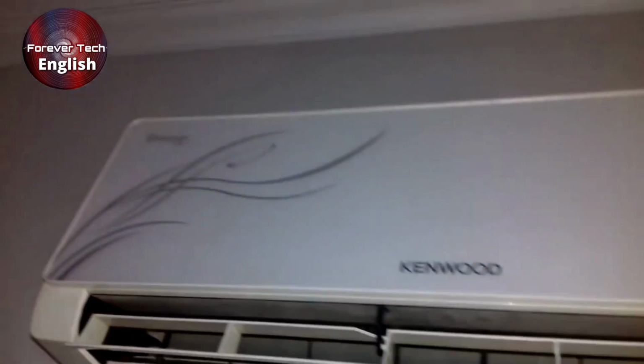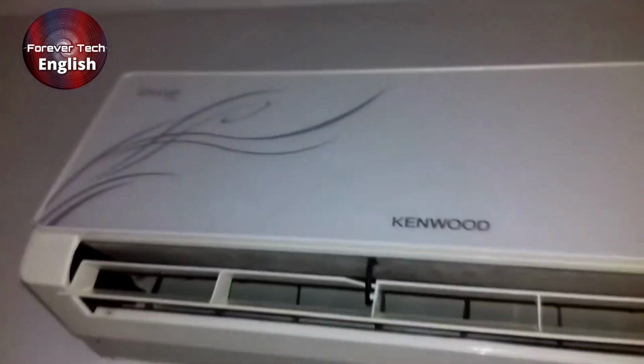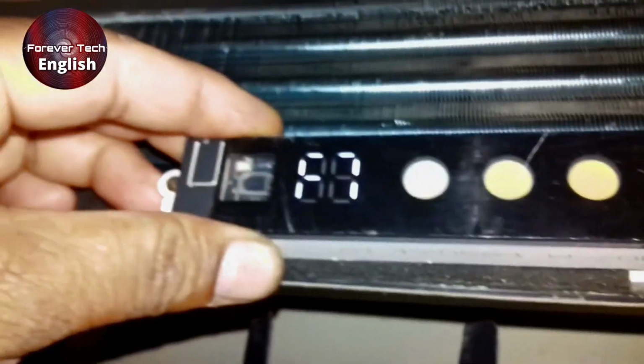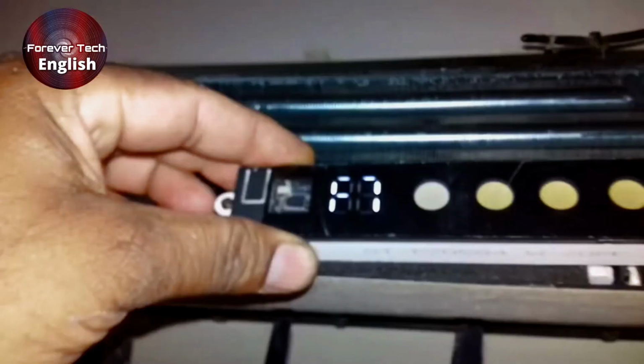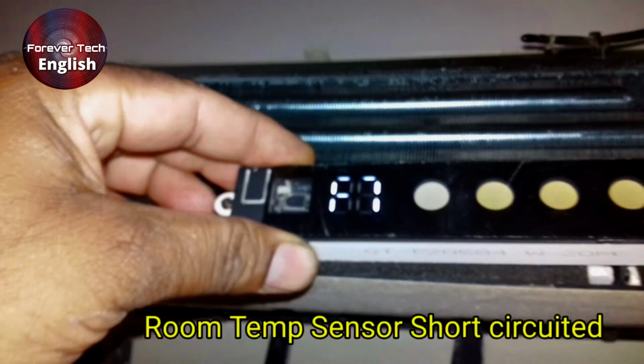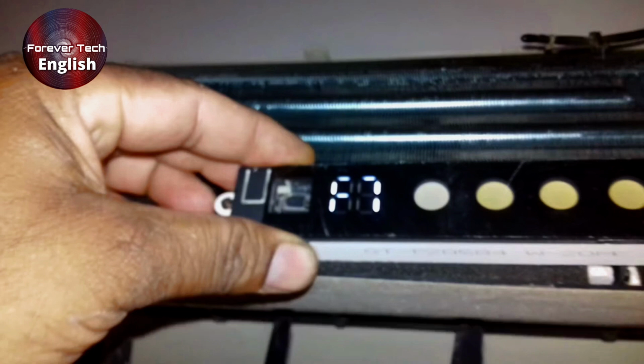I am going to talk to you about the error codes of a Kenwood air conditioner. The F7 error code has appeared on the display. Friends, the F7 code appears on the display of a Kenwood air conditioner when the ambient temperature sensor, also known as the room temperature sensor, becomes faulty. That's when the F7 error code will be displayed.